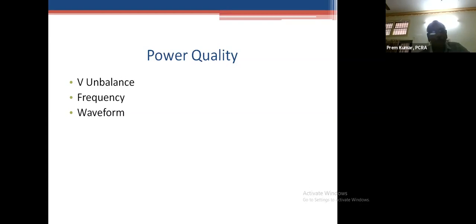Frequency is very important, and harmonics are also very important. That is what we mean by waveform. Of course, TANGEDCO has now started implementing harmonics limits as per the latest IEEE 519 standards. So whenever you are dealing with nonlinear loads, ensure that you impress upon the manufacturer to take the necessary checks and steps, such as filters or chokes, and follow the installation guidelines to ensure a minimum of harmonics.